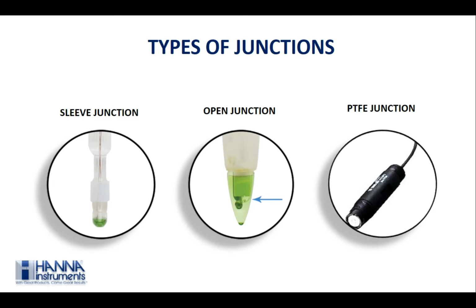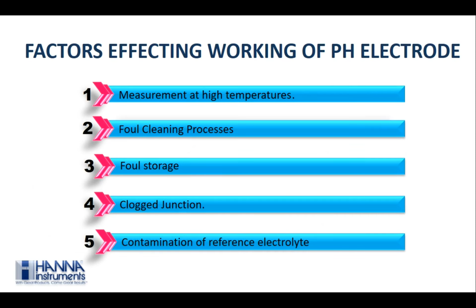Even after such a fortified design of an electrode with all these types of junctions, what are the other factors that affect the working of a pH electrode? So let's accept that the life of a pH electrode is very short. It does not last forever. The factors that affect the working of a pH electrode can be high temperatures, cleaning processes, storage, clogging of the junction, contamination of reference electrolyte. All these factors go hand in hand.